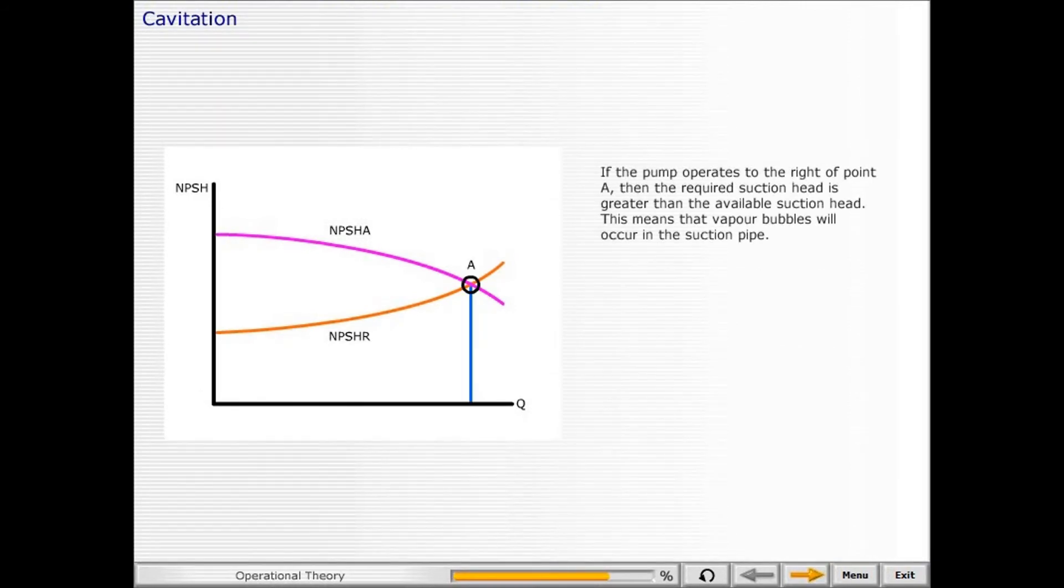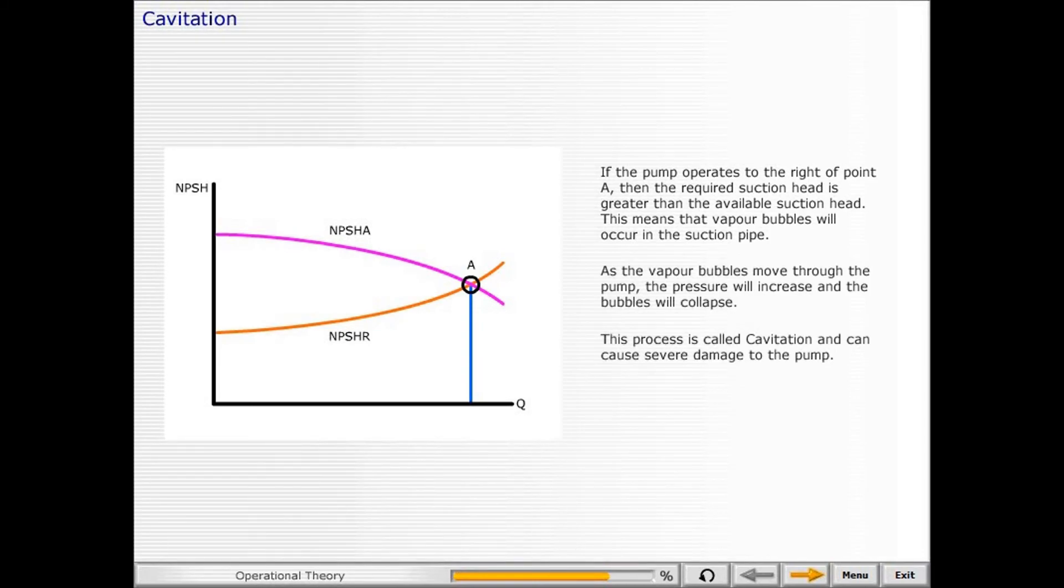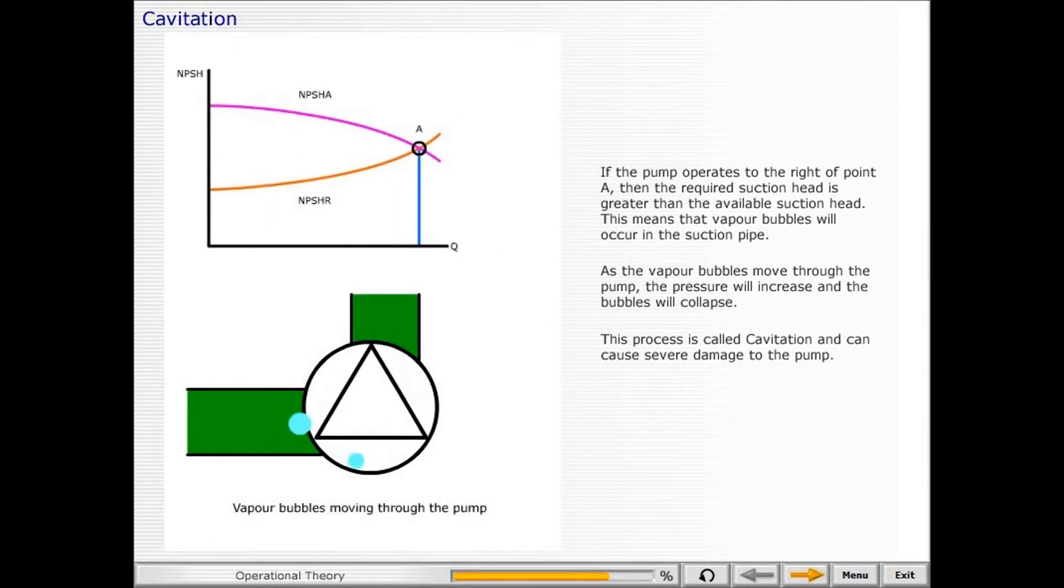If the pump operates to the right of point A, then the required suction head is greater than the available suction head. This means that vapor bubbles will occur in the suction pipe. As the vapor bubbles move through the pump, the pressure will increase and the bubbles will collapse. This process is called cavitation and can cause severe damage to the pump. Operation to the left of point A means that vapor bubbles will not form, and so cavitation will not be a problem.